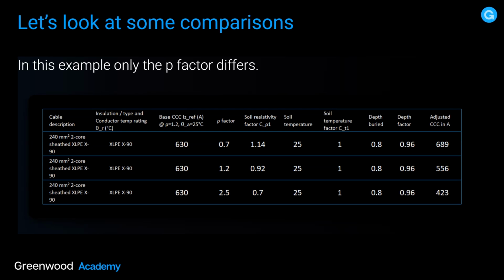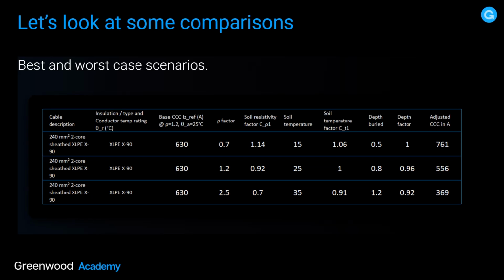And you're looking at 423 amps. Soil thermal resistivity really plays quite a proportionally large role in reducing or increasing the current carrying capacity depending on that level. So the lower the soil thermal resistivity, the better the actual current carrying capacity of the cable, all other things being equal. Let's look at some best and worst case scenarios.